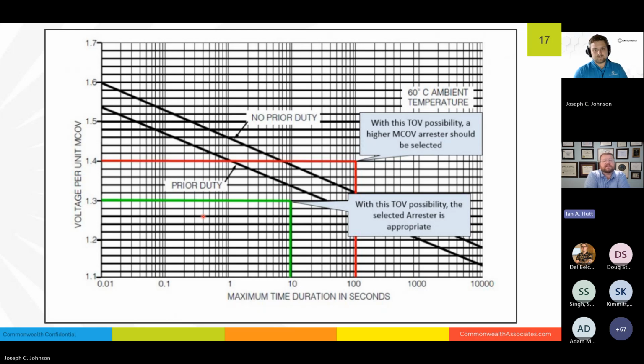So, talking about TOV, and again, we're not going to get too deep, but just touch on it at a high level because it is related to arrestor selection and sizing. TOV is very sensitive to time. So, how long will these TOV events last? And this goes into protection. When we talk about protection margins, generally we try to think in the realm of a few cycles to maybe 2 to 10 cycles, depending on your protection schemes, your backup protection levels, and breaker failure events, things like that.